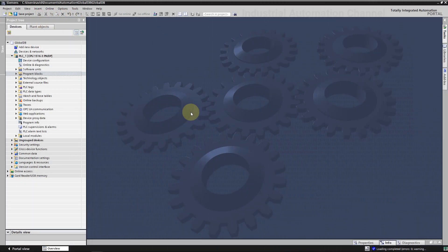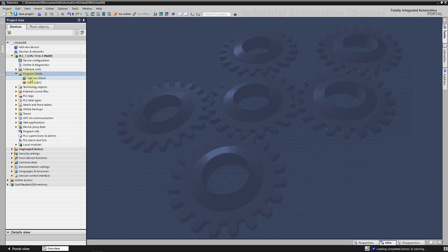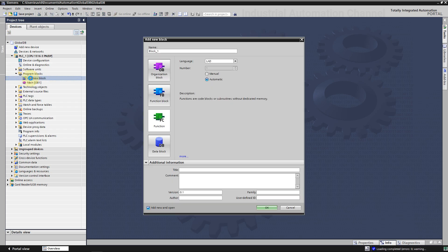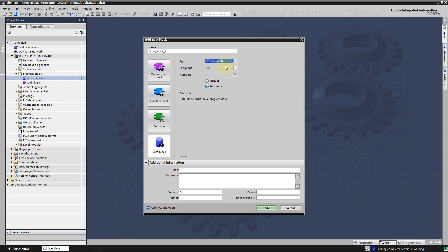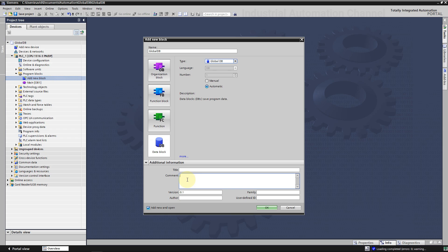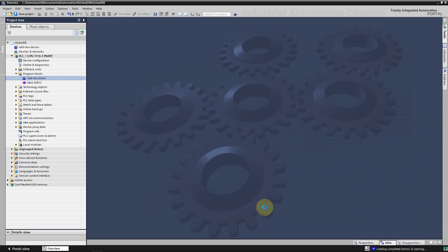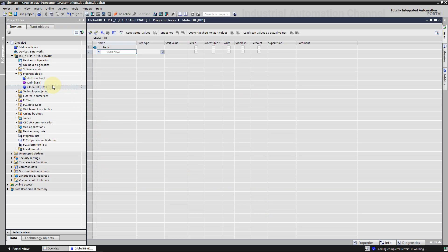Let's see how we can create and use a global data block in TIA Portal. We can create a global data block the same way we create a function or a function block. In the project tree, open program blocks and double click add new block. Click the data block DB button and select the type of data block as global. You can assign a number to this DB manually or let TIA do it automatically. Enter a name for the DB. You can enter all the properties you require under additional information. Hit OK. The new data block is created. You can find it here in the program blocks folder.